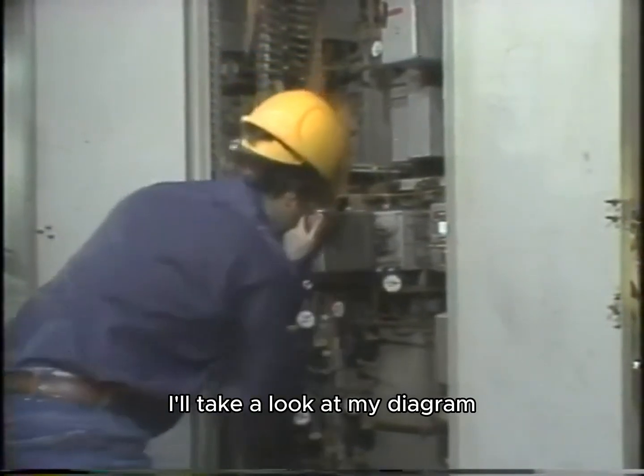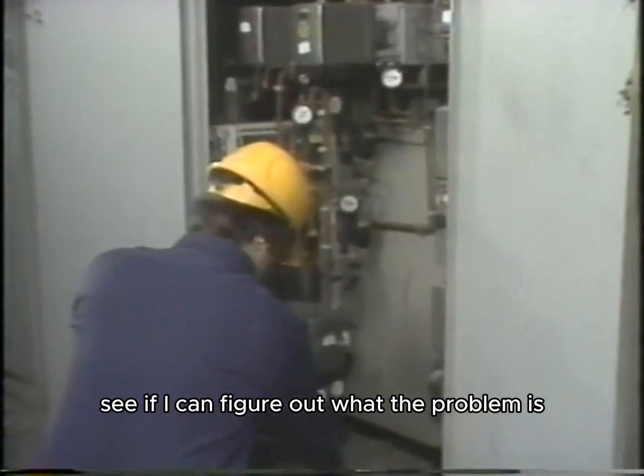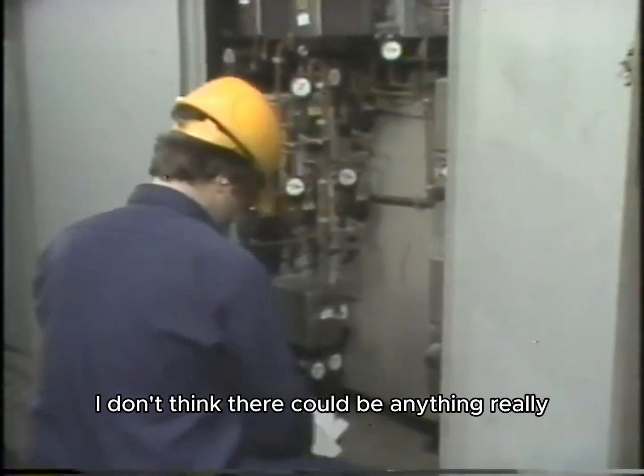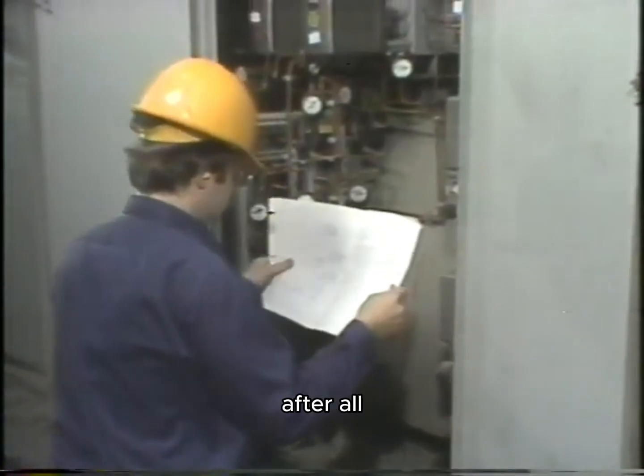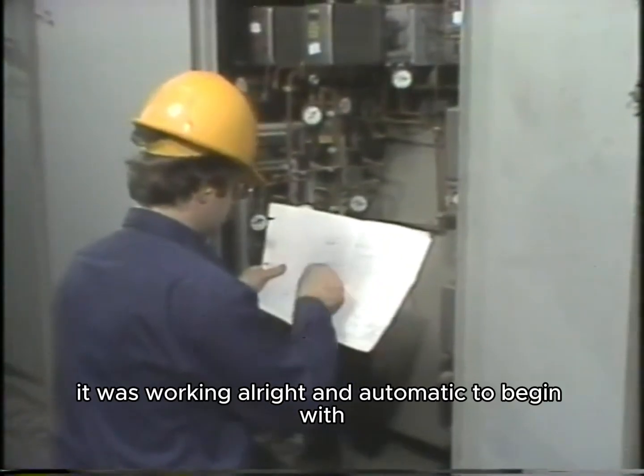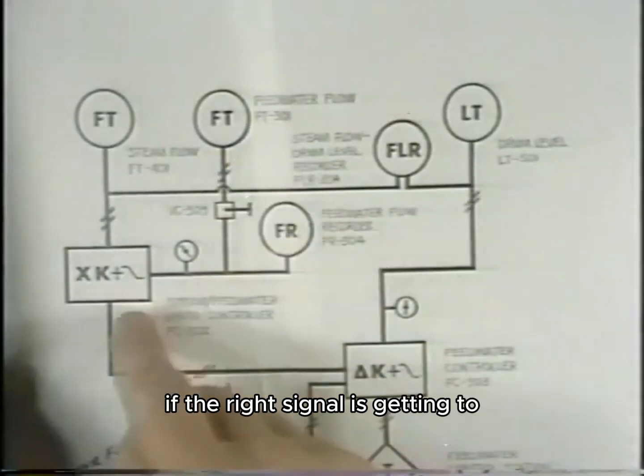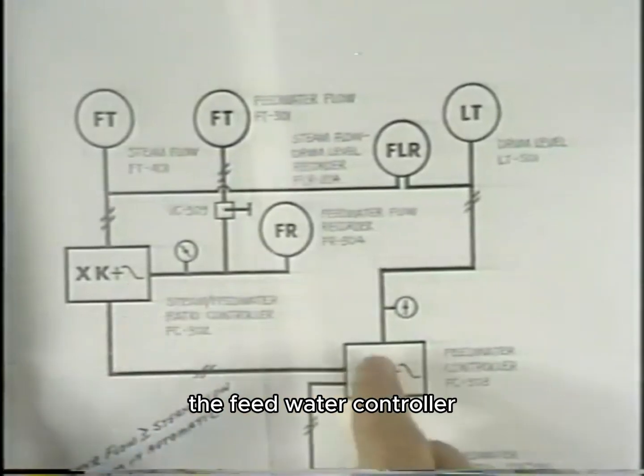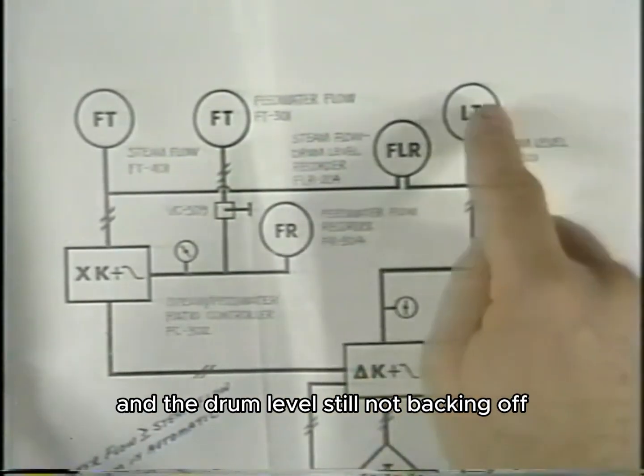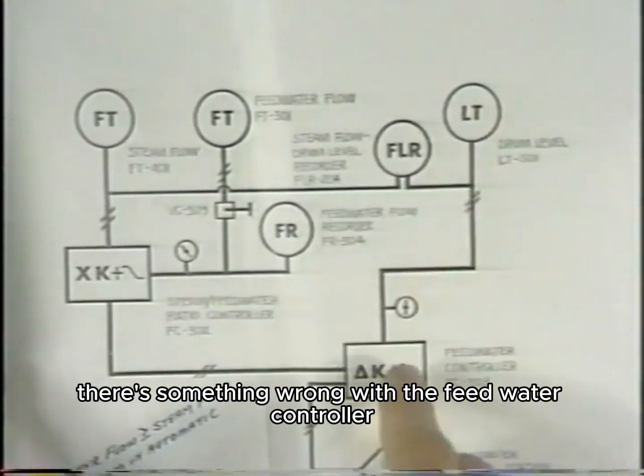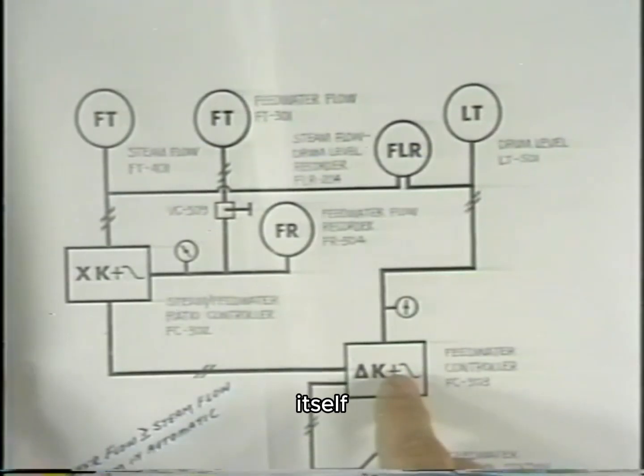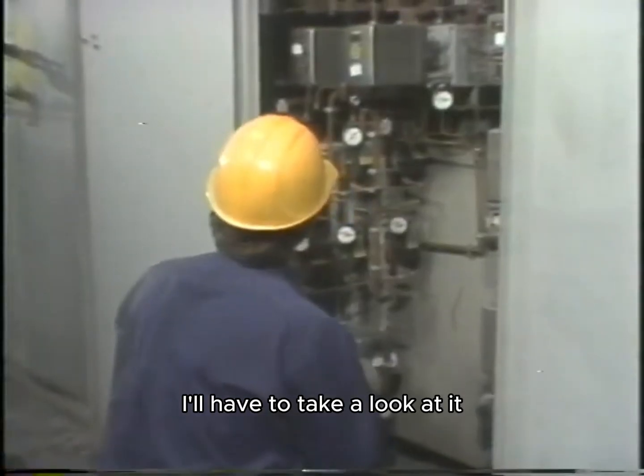I'll take a look at my diagram, see if I can figure out what the problem is. I don't think there could be anything really seriously wrong with the controller. After all, it was working all right in automatic to begin with. If the right signal is getting to the feed water controller and the drum level is still not backing off, maybe there's something wrong with the feed water controller itself. I'll have to take a look at it.